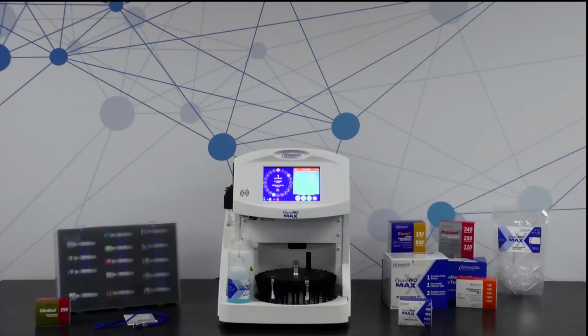How do you replace a probe if it is bent? That's going to require a field service engineering visit. Typically when the probe bumps into something, it's not going to bend because it's not coming down with enough force. But sometimes, from attempting to remove the turntable when the probe is sampling, or attempting to get in there and actually move the gantry or the probe with your hands, that's very easily going to bend the probe. So you want to make sure you avoid doing anything like that. But any bent probe will require a field service engineering visit for repair.